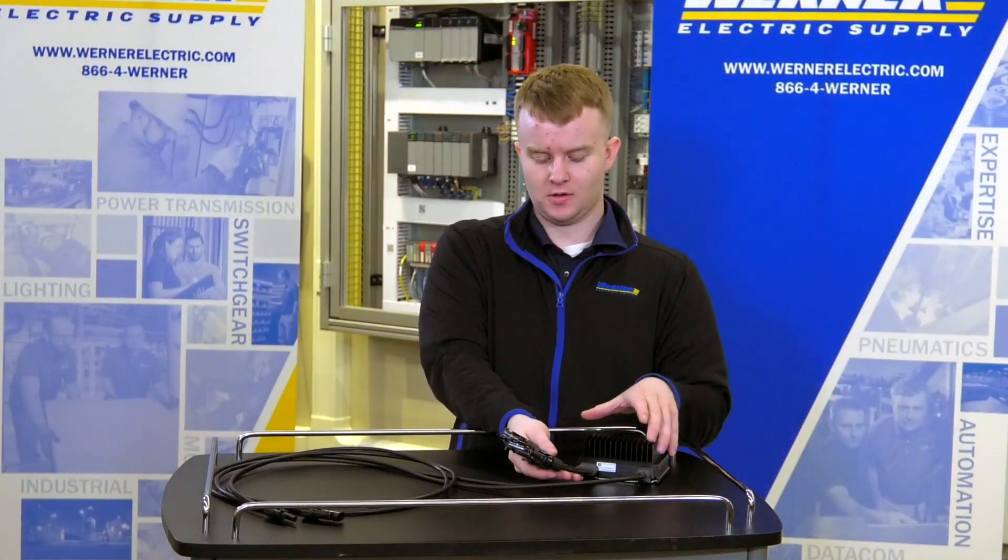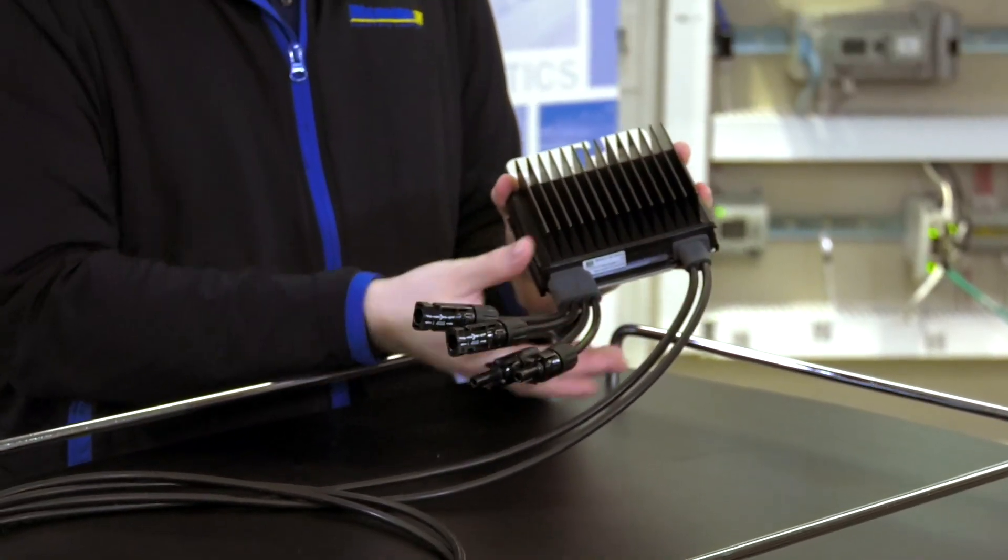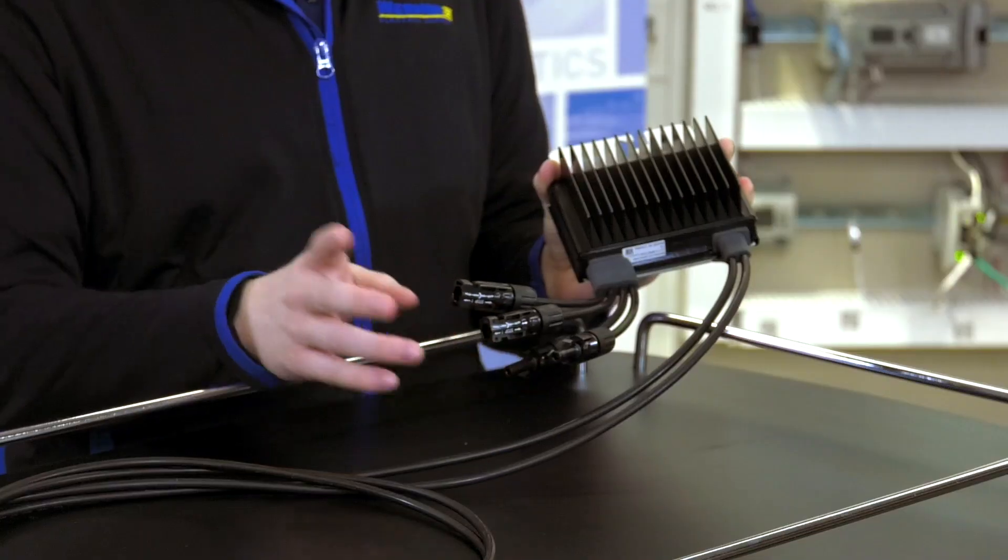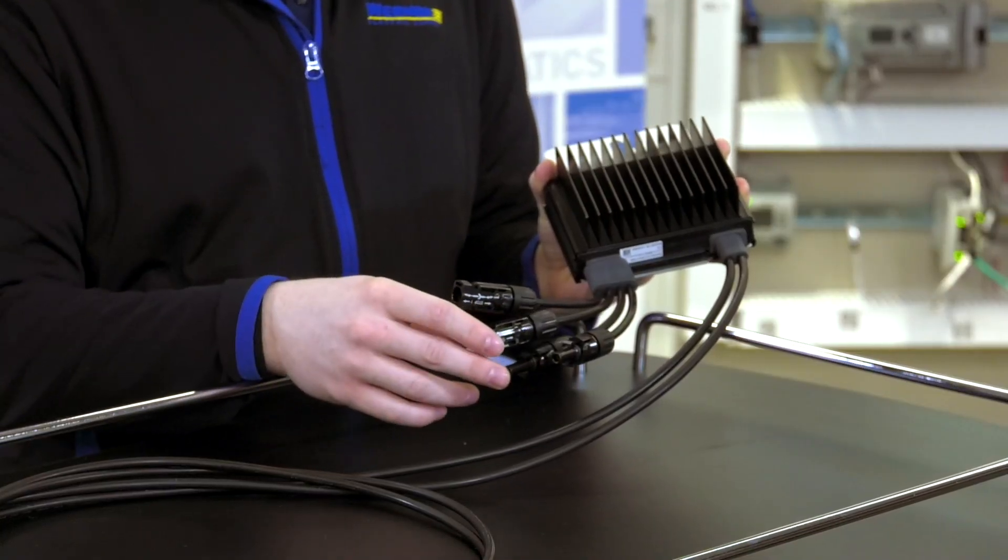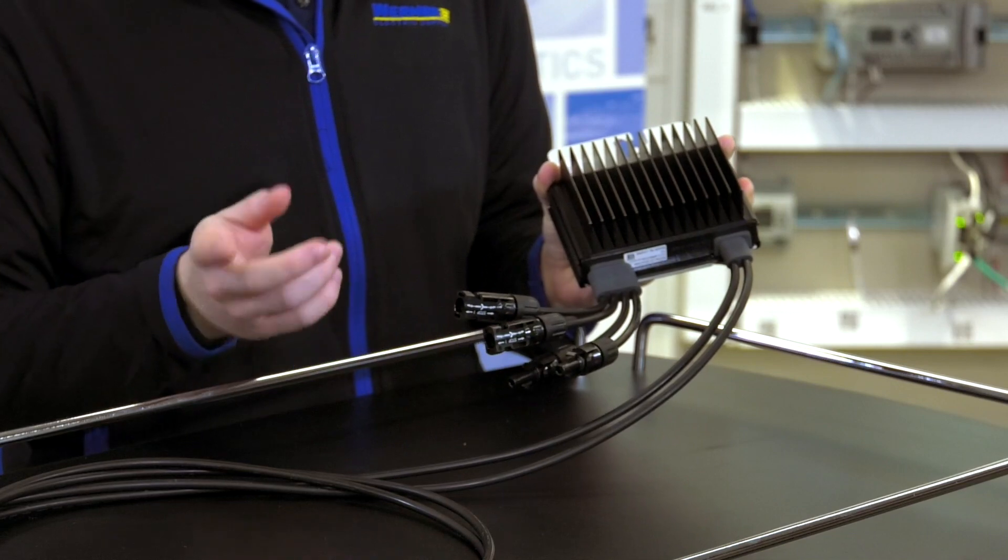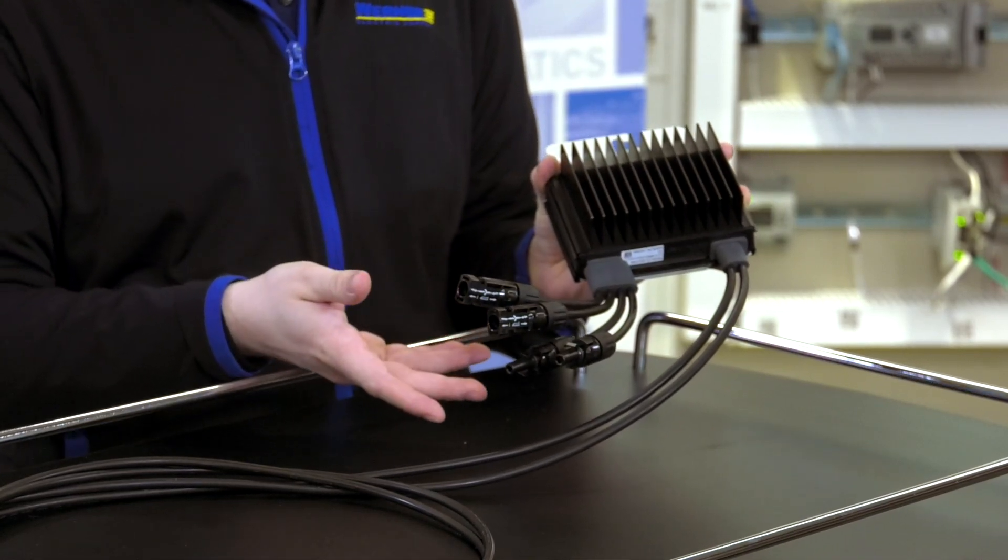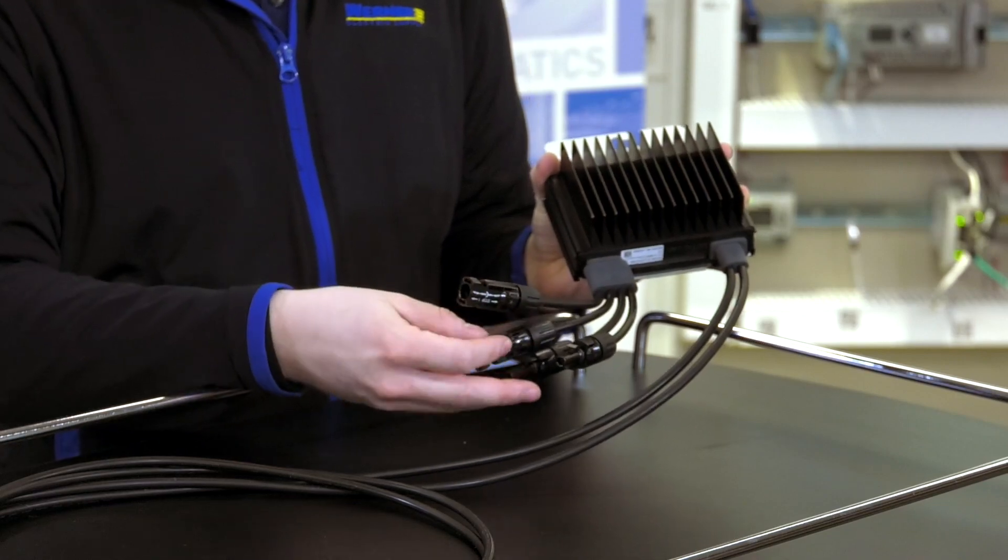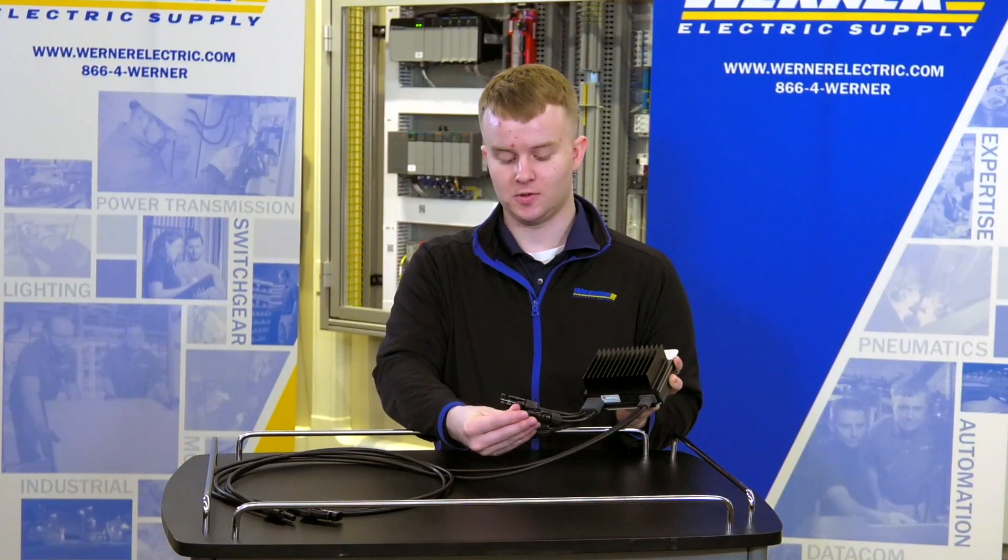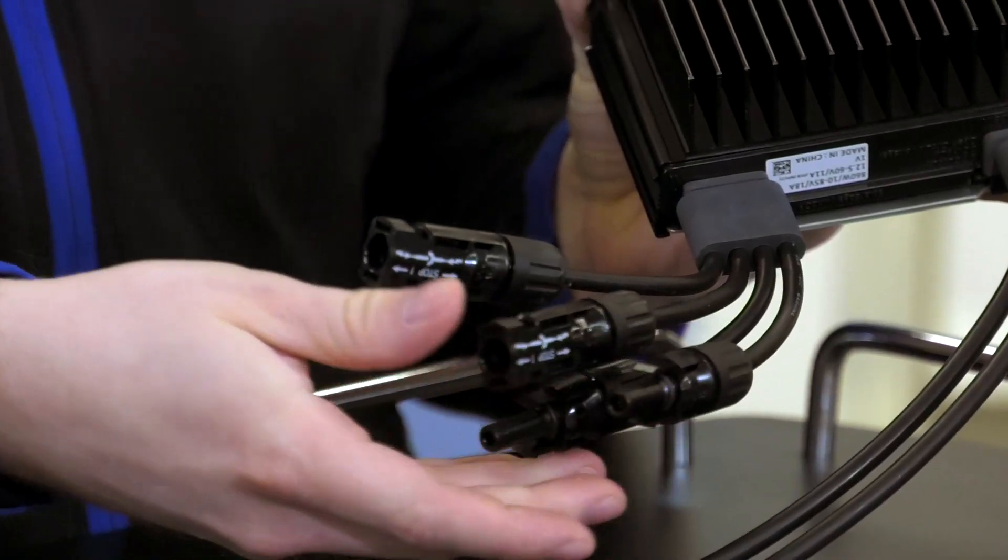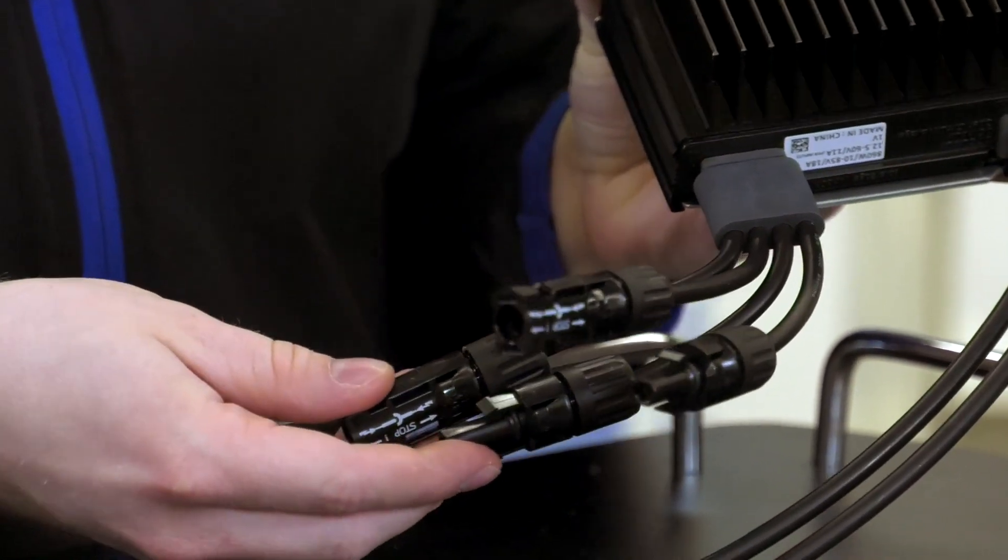These are the input cables right here. You'll connect to two different solar modules. The solar modules are wired in parallel, which is how you meet the module level shutdown code requirement. One would be going with these two cables right here and then the other solar module with these two.